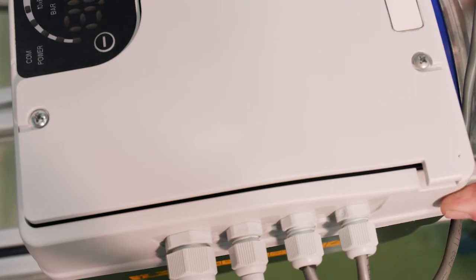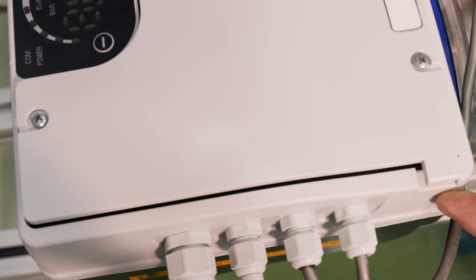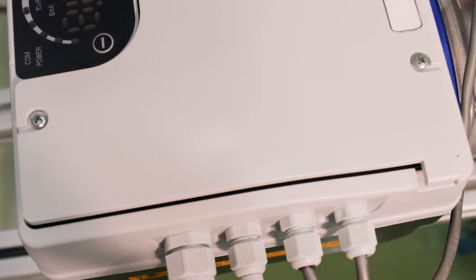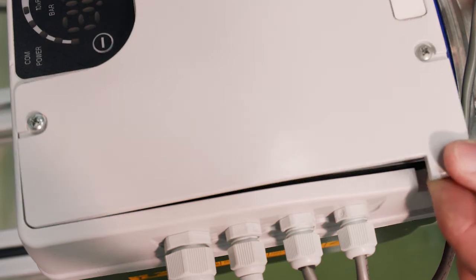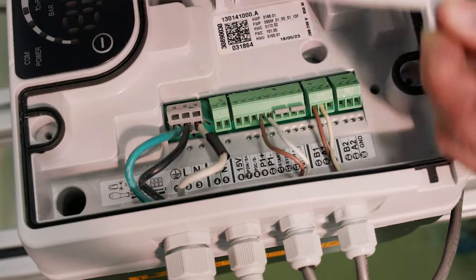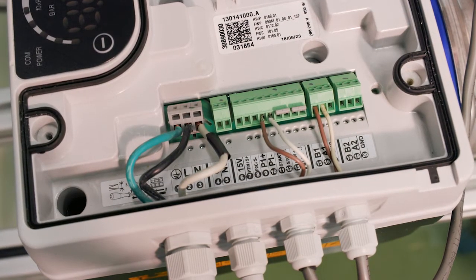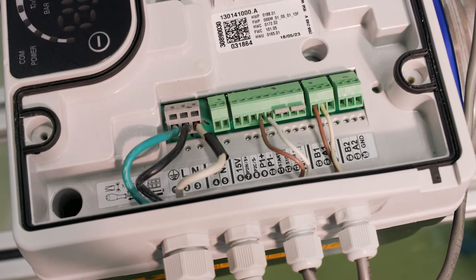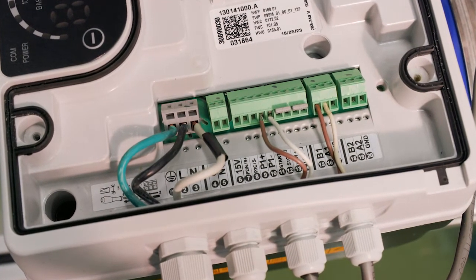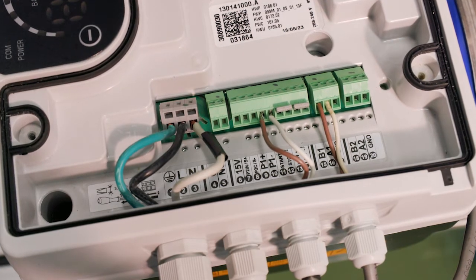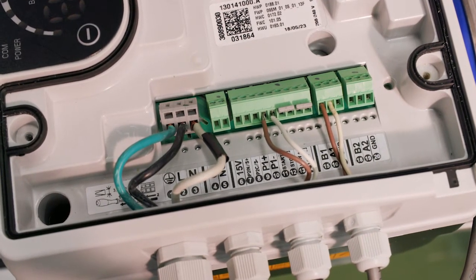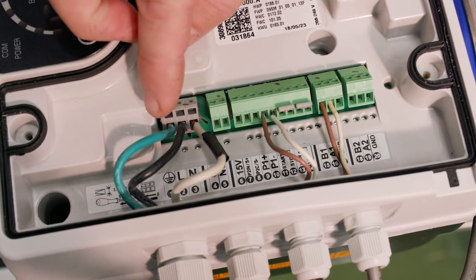Really, there's always two steps with commissioning a duplex system. The first thing that we'll cover is the wiring. We can see we've got 4 screws here. We've already loosened them up, and we're just going to take the cover off. We are going to be looking at just one unit here, and the other unit is going to be wired exactly the same. So we're going to start from left to right.